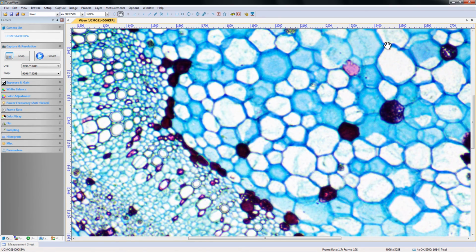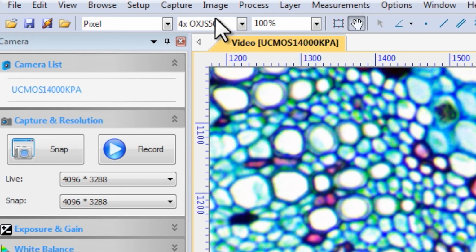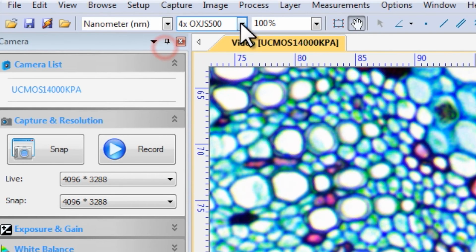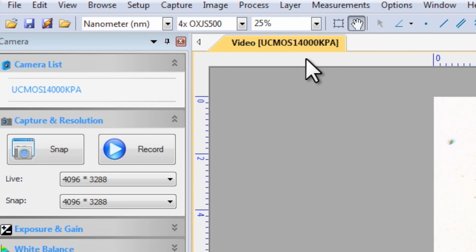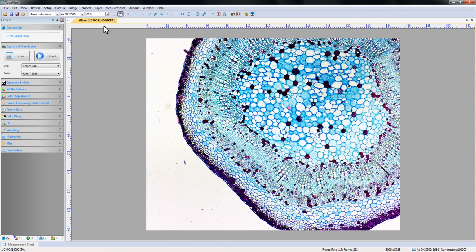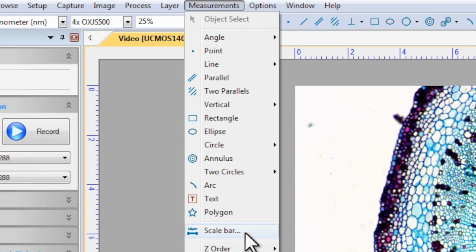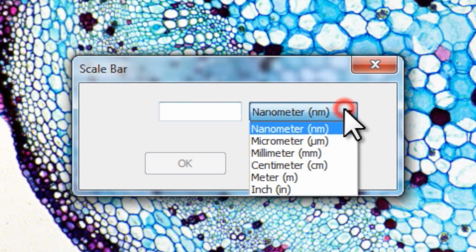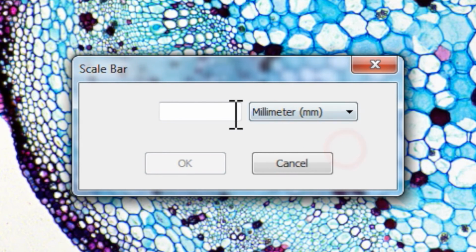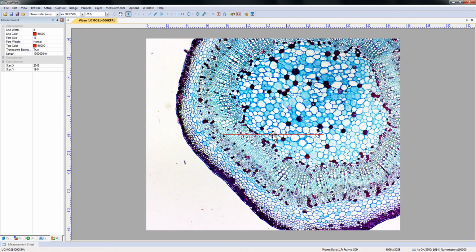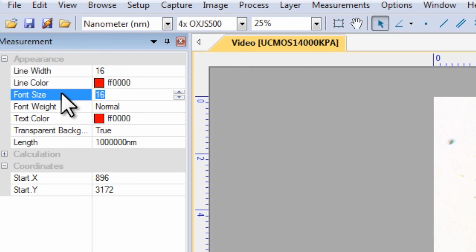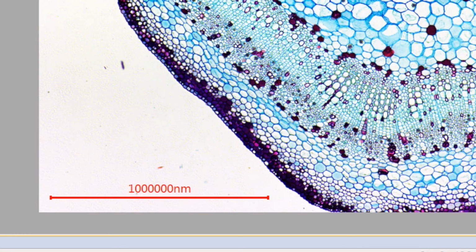To apply a scale bar, return your specimen to the stage and refocus. Select what unit of measure you want your scale to read in using the drop-down menu. Make sure that the next drop-down menu shows the magnification that you just calibrated. The digital magnification may now be changed without affecting the measurements. To add the scale, go to the Measurements menu and select Scale Bar. It is now asking you how long you want the bar to be. If we select 1 mm, it will give a 1 mm long bar that reads 1 million nanometers. You can alter the measurement properties in the panel on the left. It is often handy to increase the line width and font size.